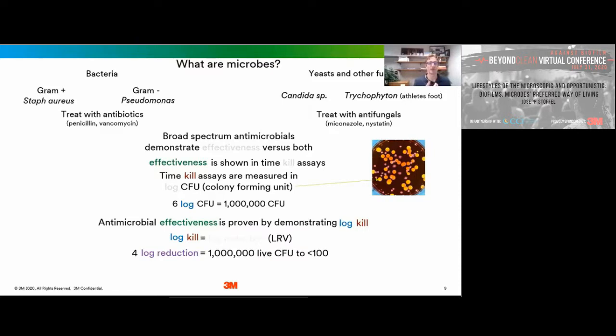For example, a 4 log reduction is generated by taking 1 million living CFUs and reducing it down to less than 100 survivors. If this wasn't confusing enough, we can also describe that 4 log reduction as 99.99% effective. A 4 log reduction is important from a combination device standpoint, but from a high-level disinfection standpoint, typically depending on the method and the claim you're going for, you're going to need to see 6 or 7 log reduction.